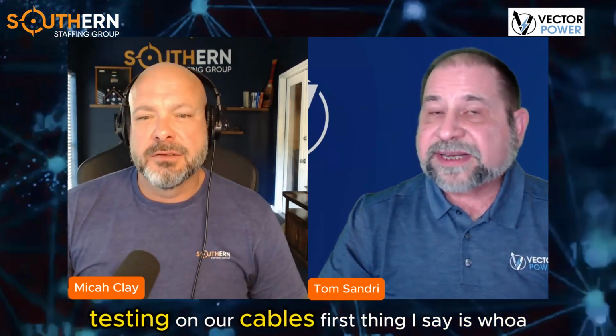So even before I talk to an industrial client who says, hey, we'd love for you to come out, we've got this open paycheck, we're willing to let you do PD testing on our cables, the first thing I say is, whoa, slow down. I don't even know if you're a contender for the technology. You're using ribbon or tape shield cables. When's your next scheduled outage? What I'll do is go out there with my pulse calibrator and equipment, send a signal in, and see how far I can measure on these type of circuits.